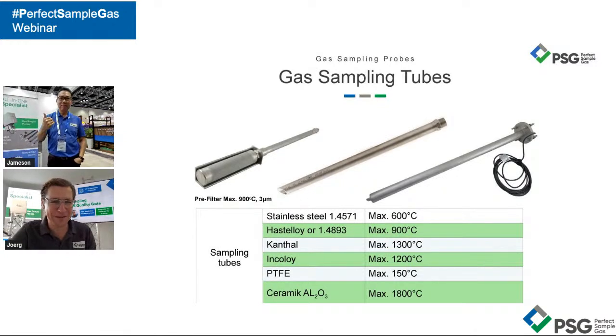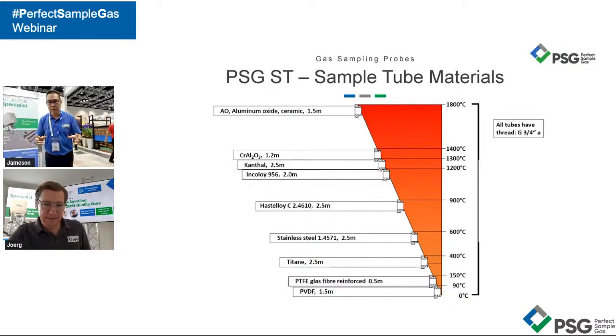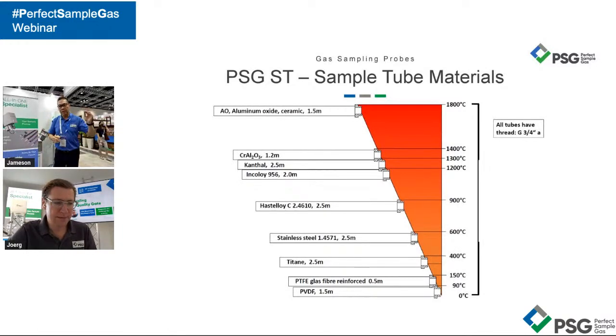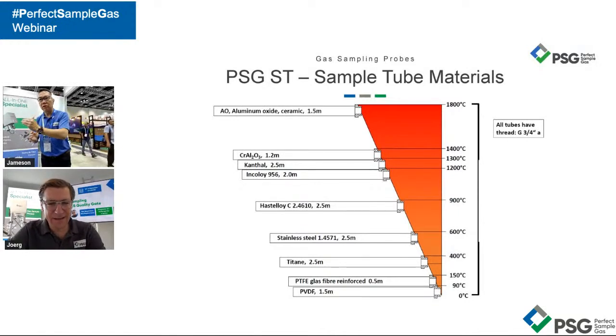So let me put you back on speaker. Yeah, this is one very important point about the sample heater tube. I always have a challenge explaining to customers that the gas is saturated with water. Many people thought that as long as they find, for example, a PTFE sample pipe, they can overcome the corrosion. This is not enough, because if the sample is saturated with water, it enters directly into our sample probe, which is at 180 degrees. It's going to be like a steam bath right inside. So the only solution is a heated sample pipe, so that the journey along the way is heated.